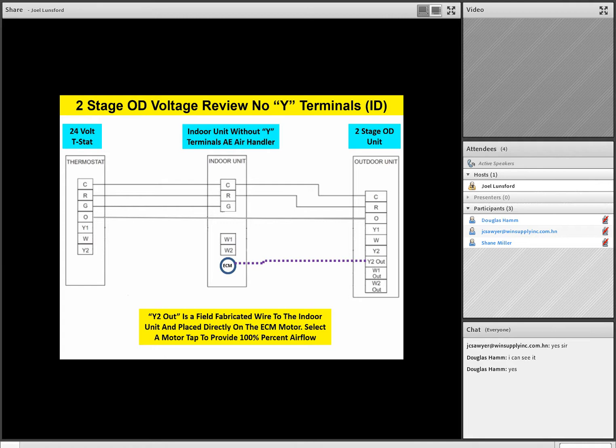It's a 24-volt signal, and then he will field fabricate just a spade terminal on the end of that thermostat wire that he brings in from Y2 out, and he'll land it directly onto the ECM motor, the desired speed tap or motor tap, to provide 100% airflow. And so, team, this is really important also. We remember that on an ECM type of motor, if that ECM motor has multiple speed commands, they're going to be 24-volt commands. If it has multiple speed commands, the ECM motor always drives to the highest speed command that it's receiving.